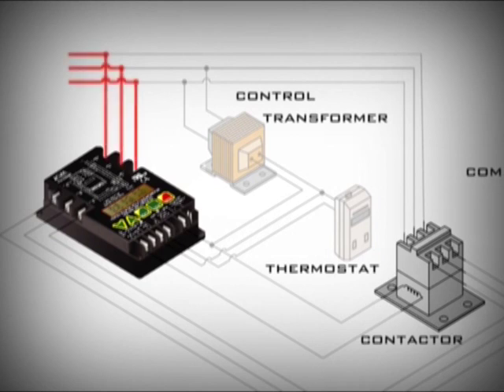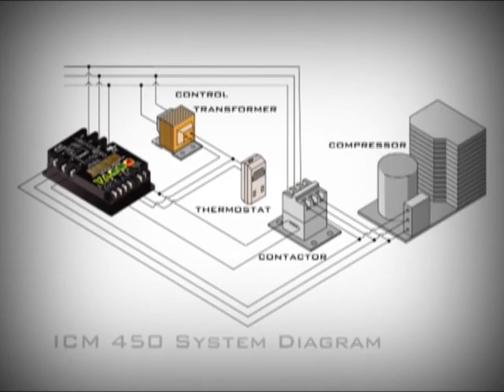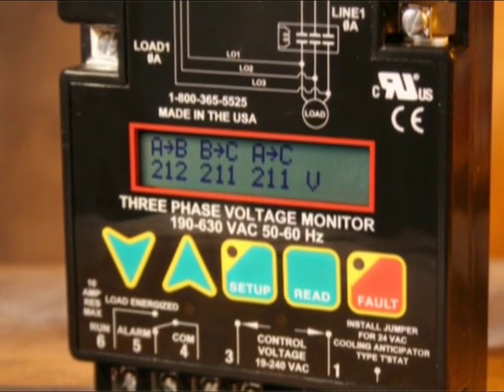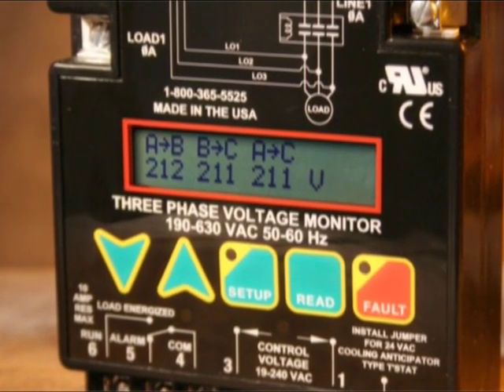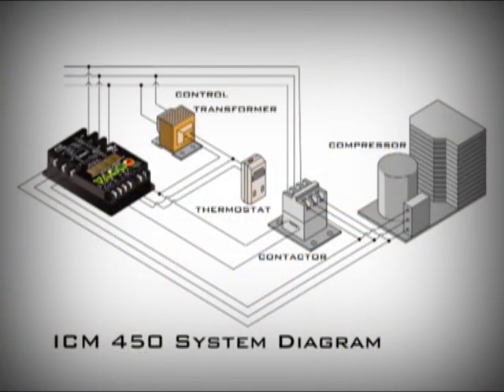At power-up, the ICM 450 checks the incoming power for proper phase sequence, amplitude, and balance. If the power is within the user-adjustable parameters, it then energizes the control circuit to connect the compressor or other load. It continuously monitors the load, and if a fault condition such as an imbalance or high or low voltage occurs, it de-energizes the control circuit to cut off power to the load. The event is also recorded for later review, so the compressor is protected continuously and automatically.